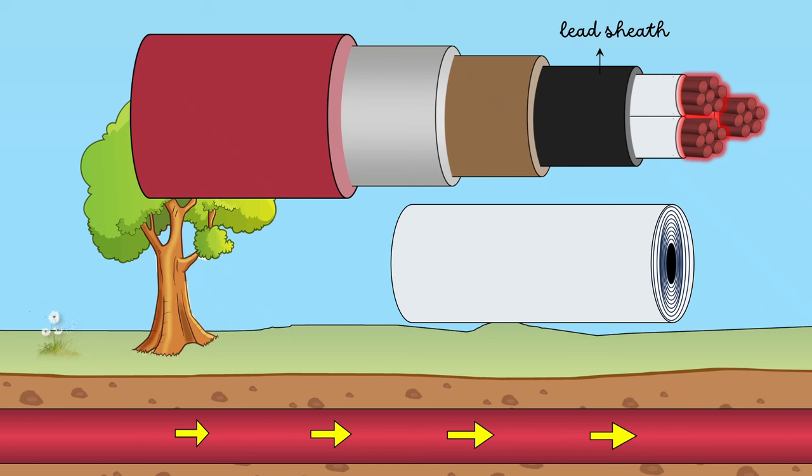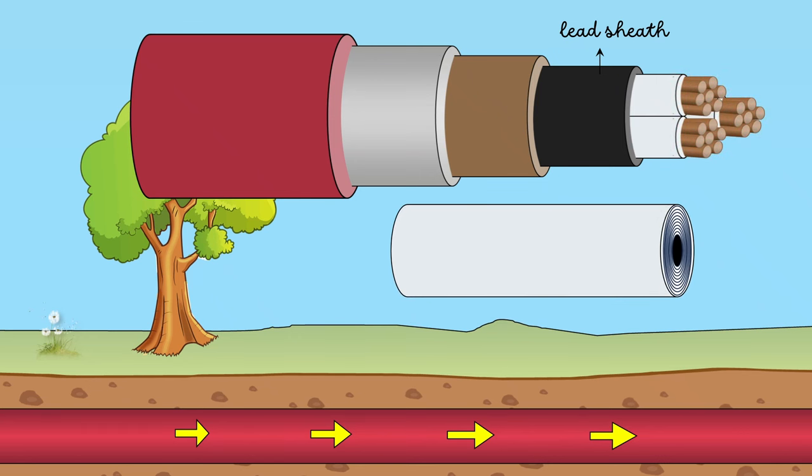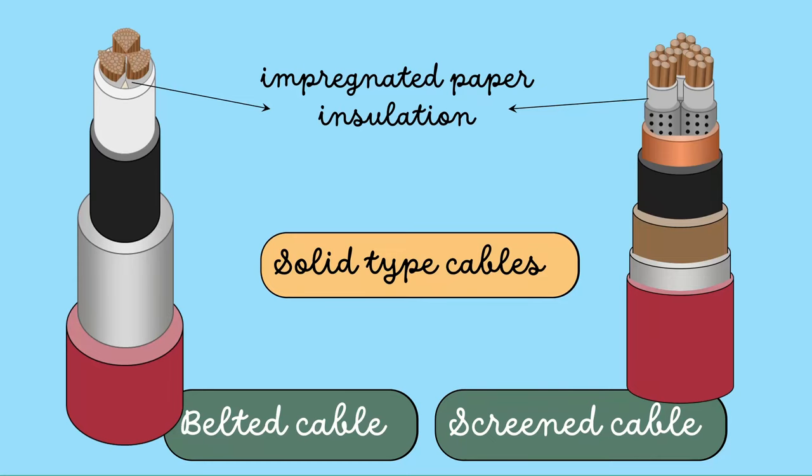When the load on the cable decreases, the conductor cools and the paper insulation contracts. This may result in the formation of voids. Voids are nothing but vacant spaces. They may cause permanent damage to paper insulation. Therefore, for higher voltages beyond 66 kV, these solid type cables are not recommended.